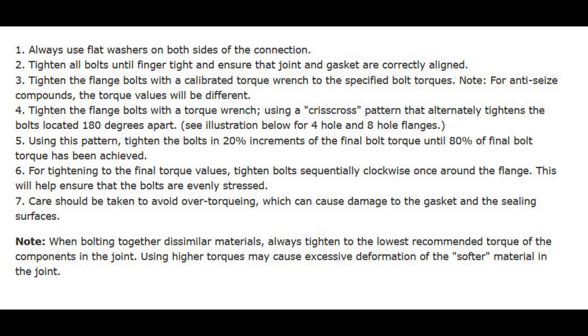Number 7: Care should be taken to avoid over-torquing, which can cause damage to the gasket and the sealing surfaces. Note: when bolting together dissimilar materials, always tighten to the lowest recommended torque of the components in the joint. Using higher torques may cause excessive deformation of the softer material in the joint. I hope this video is useful for you.